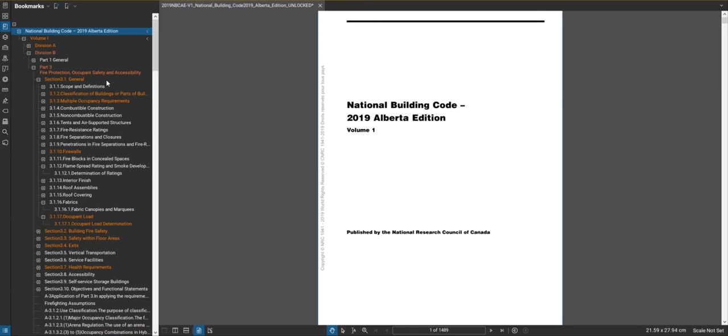As an example of that, the total cumulative width of egress doors from a suite would be based off occupant load, the width of a corridor would be based off occupant load, the width of exit stairs would be based off occupant load, and the width of an exit is based off occupant load. So many of the life safety parameters of the building are based off the occupant load calculation results.